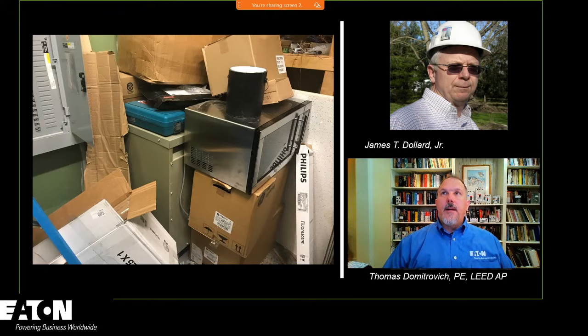The image on screen right now is that transformer, and I put it up because I think it leads us into the next question a bit. When you see a facility that isn't well maintained or does things like this, remember a transformer is supposed to be ventilated, with air circulation and so on. Obviously in this image, you're not applying that product correctly. If that facility is full of these issues, with openings in equipment that shouldn't be there, it's not well maintained. When a power distribution system isn't being maintained or appropriately treated, you could have unintended hazards in that room or those areas of your plant, and you may need to treat it differently because the equipment hasn't been maintained correctly.